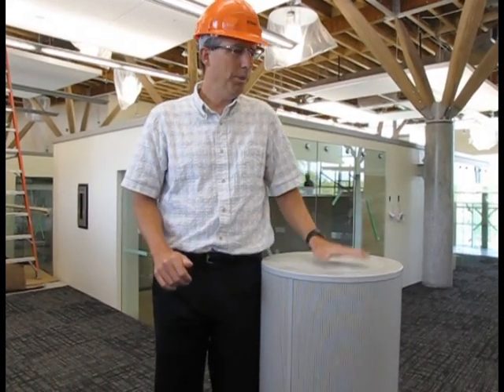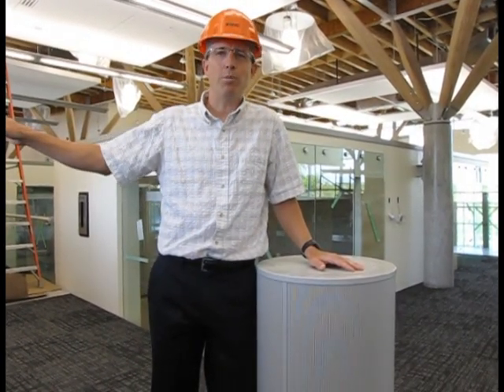We're using some old style technology too. Helping to cool the building, we have earth tubes buried in the ground adjacent to the parking lot. These are like 4-foot diameter concrete tubes that are underground horizontally, but they have an end point where the air can be drawn in from outside through those tubes, and then it enters the building. So the air is pre-cooled in the summer to help reduce the load on the cooling system. In the winter, we have another passive feature. We have what we call solar walls, which we can show you a video of in a minute, where we try and preheat the air as it comes in. So that's all just to offset things.